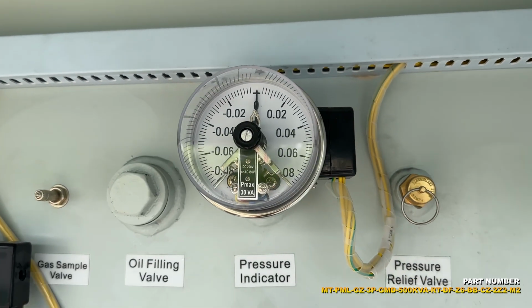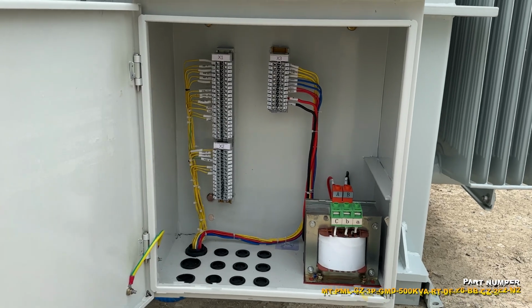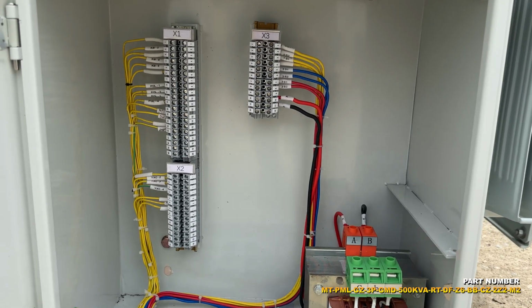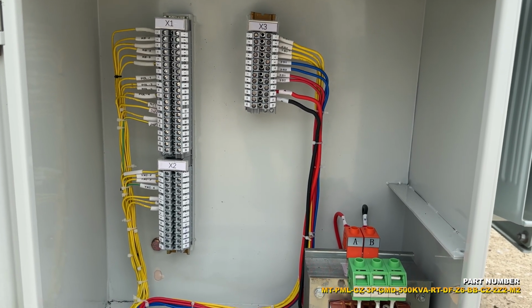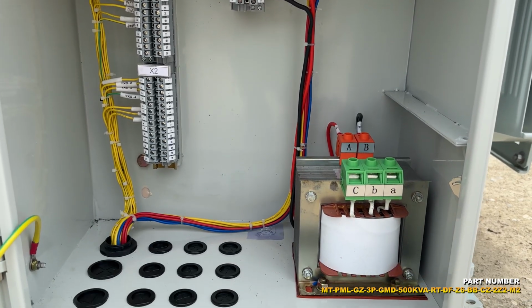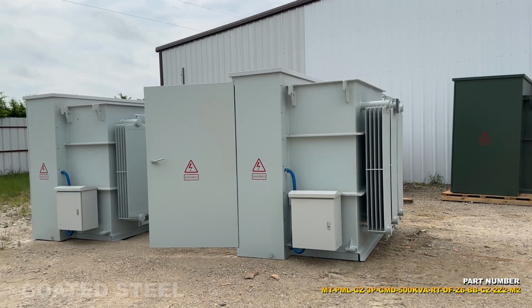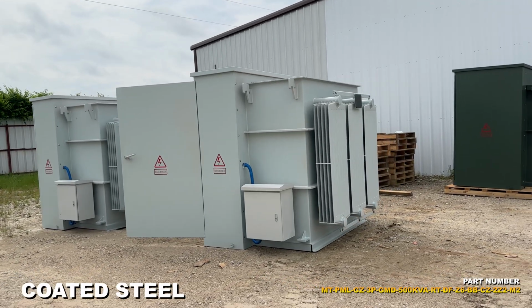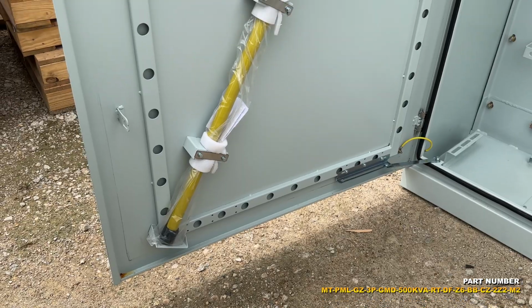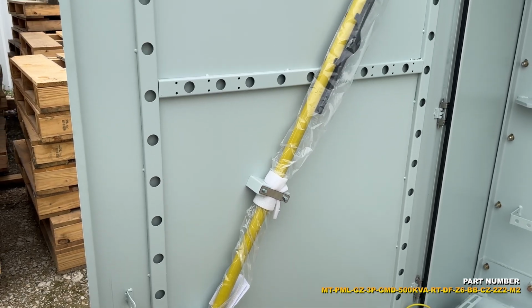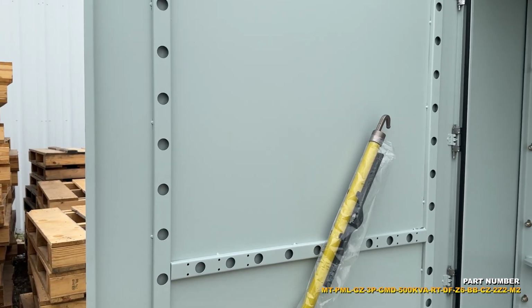The standard NEMA Type 3R enclosure makes the unit suitable for both indoor and outdoor applications, and it can be pad mounted. This unit also features mineral oil cooling, Class A insulation, and is designed so that no excess oil heating occurs from unbalanced loads or phase loss on the primary side.